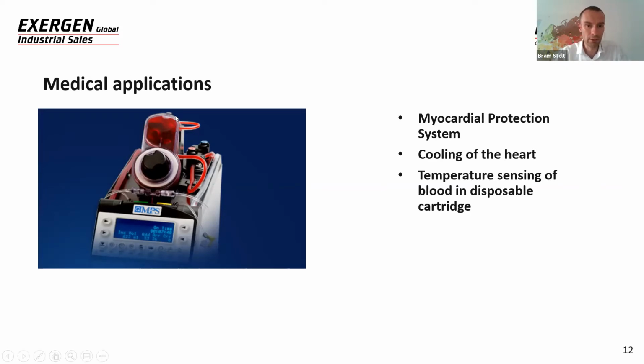And what you see here is a disposable cartridge that can be clicked on this device. On the back of this is one of our IR sensors that is calibrated in such a way that it measures the blood that is in the cartridge. It measures through the wall of the cartridge, and it measures the blood to ensure that there is sufficient cooling to protect the heart tissue.